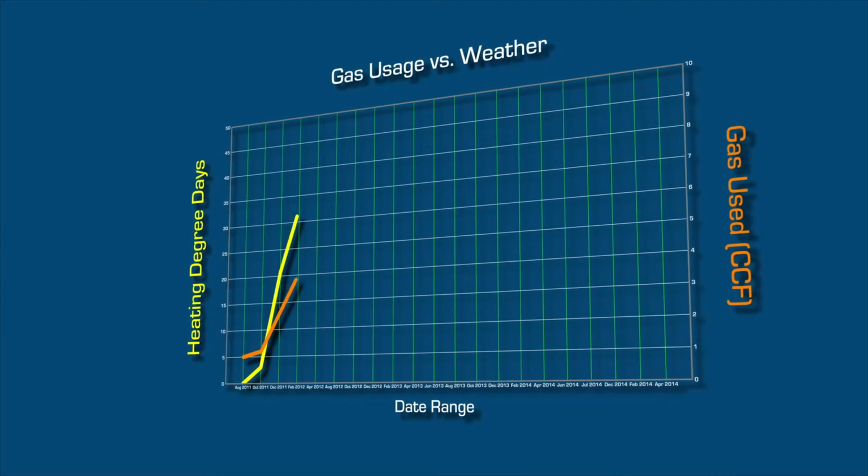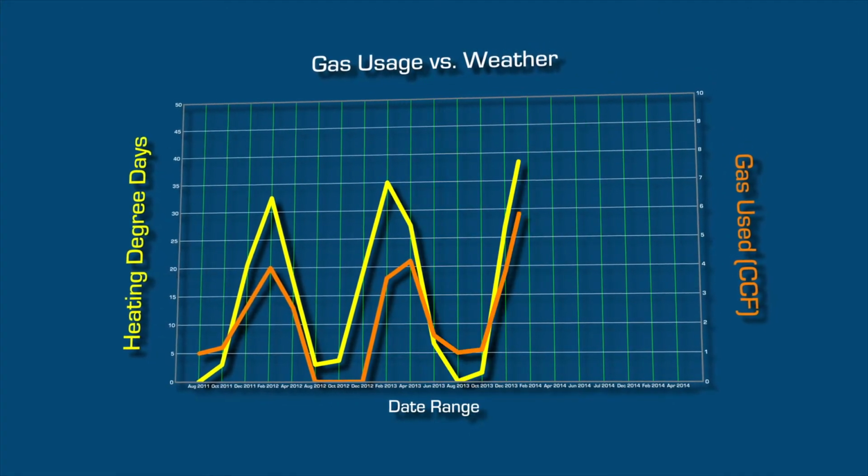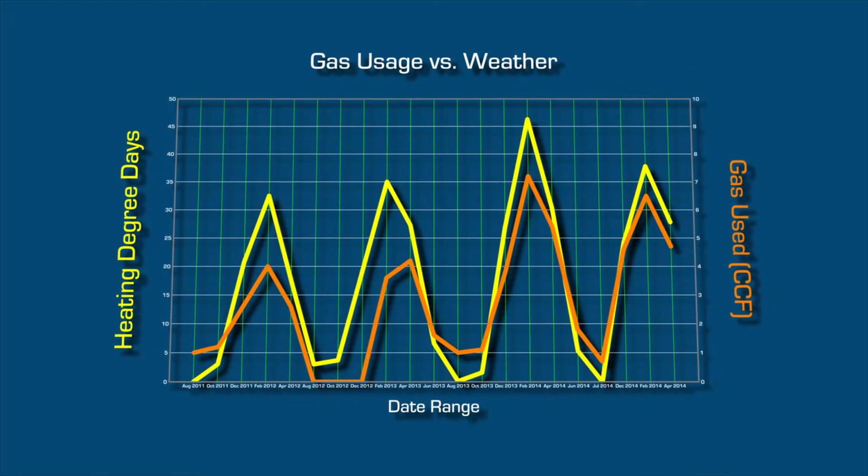One of the things that we tend to see a couple times of the year, we run into people wondering if specific appliances were operating during an event. One of the ways that we can analyze this is by looking at the gas usage and take the billing data from the utility provider, look at the weather data for that time period, and we can develop a baseline gas usage prior to the subject period, and then we can predict what the expected gas usage during the period of interest would have been and compare that to what was recorded.